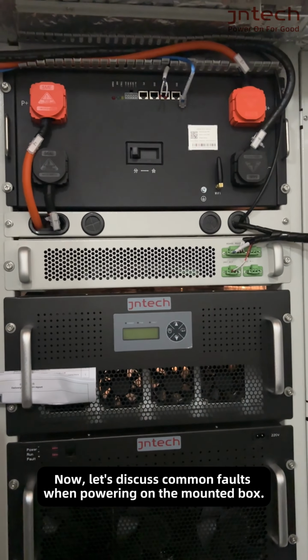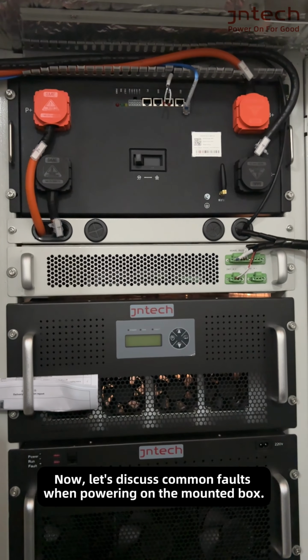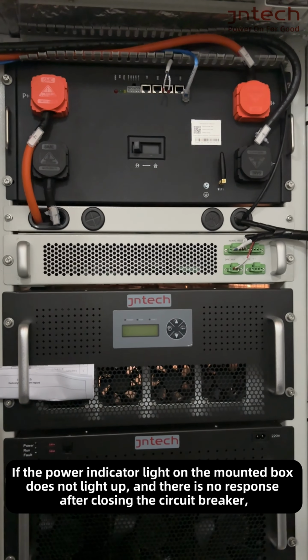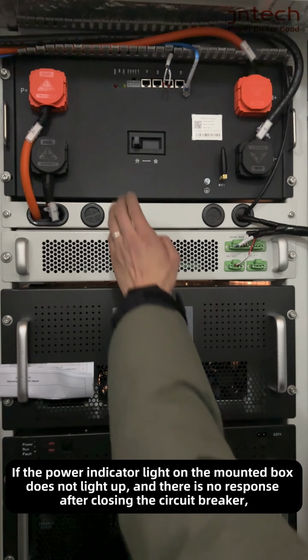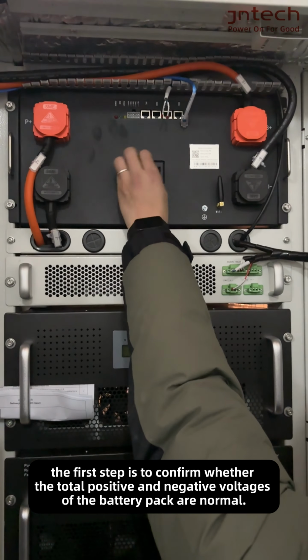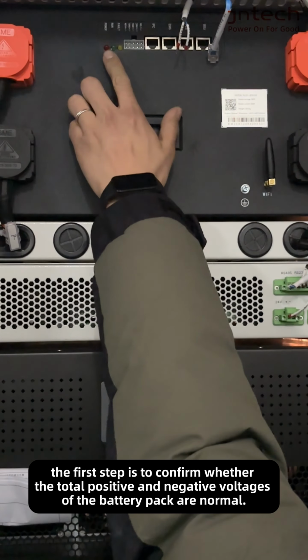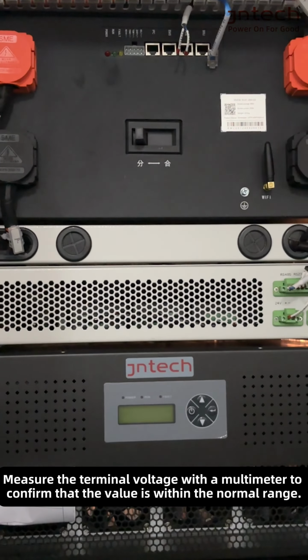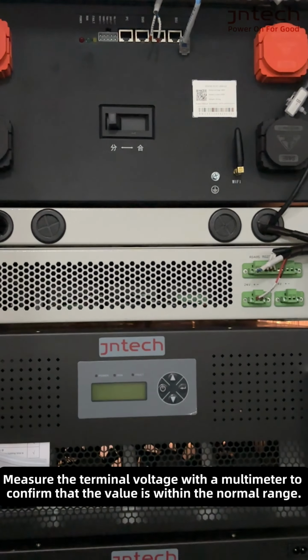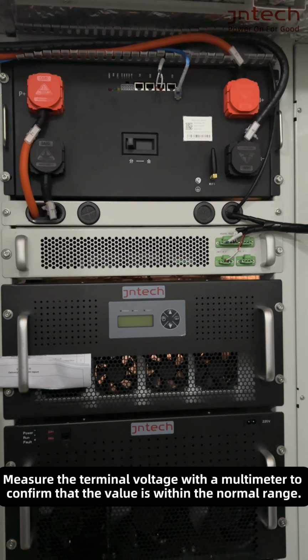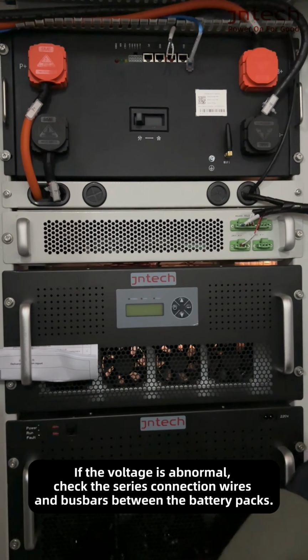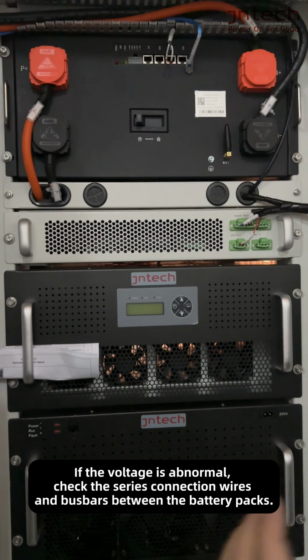Now, let's discuss common faults when powering on the mounted box. If the power indicator light on the mounted box does not light up, and there is no response after closing the circuit breaker, the first step is to confirm whether the total positive and negative voltages of the battery pack are normal. Measure the terminal voltage with a multimeter to confirm that the value is within the normal range. If the voltage is abnormal, check the series connection wires and bus bars between the battery packs.